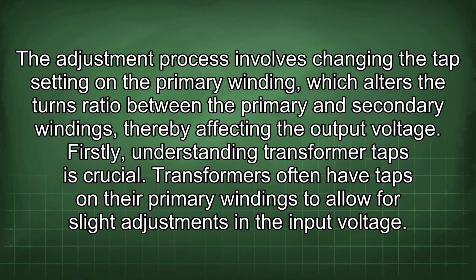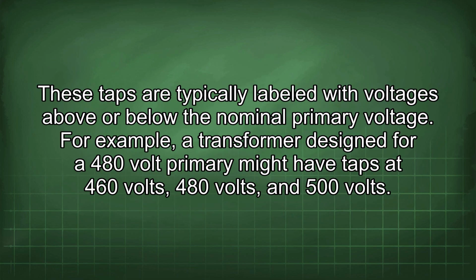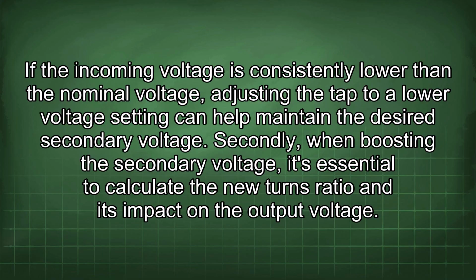Firstly, understanding transformer taps is crucial. Transformers often have taps on their primary windings to allow for slight adjustments in the input voltage. These taps are typically labeled with voltages above or below the nominal primary voltage. For example, a transformer designed for a 480-volt primary might have taps at 460 volts, 480 volts, and 500 volts. If the incoming voltage is consistently lower than the nominal voltage, adjusting the tap to a lower voltage setting can help maintain the desired secondary voltage.